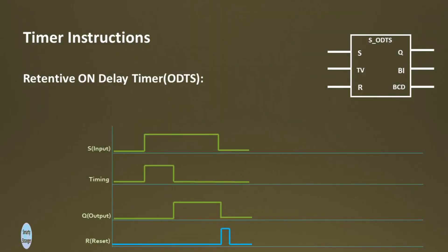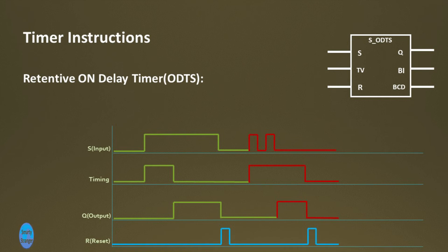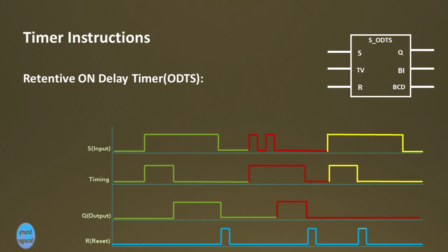Let's understand the Retentive On Delay timer via trends view. In the first cycle, if there is a positive edge at S input, the timer starts its timing, and when it completes its defined timing, output Q starts giving 1 or high. In the second cycle, if there is fluctuation on S input — meaning input changes from 1 to 0 or 0 to 1 — before time elapsed, the timer resets to its predefined value, remains in running condition, and completes its timing. In the third cycle, if input R changes from 0 to 1 while the timer is running, the timer resets immediately.